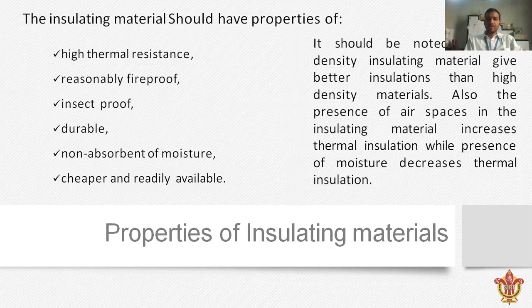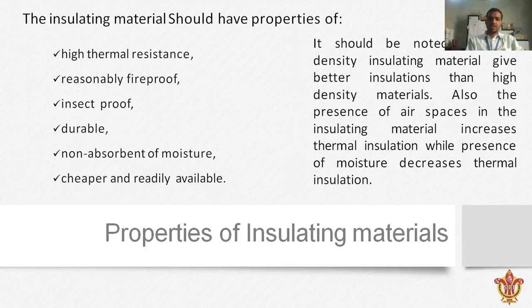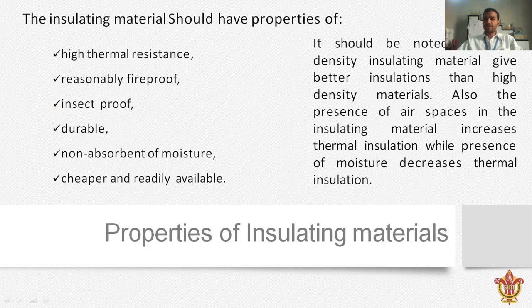The insulating material should have the following properties: high thermal resistance, be fireproof, insect-proof, durable, non-absorbent of moisture, and be cheaper and readily available. It should be noted that low-density insulating material gives better insulation than high-density material. The presence of air space in the insulating material increases thermal insulation, while the presence of moisture decreases thermal insulation.